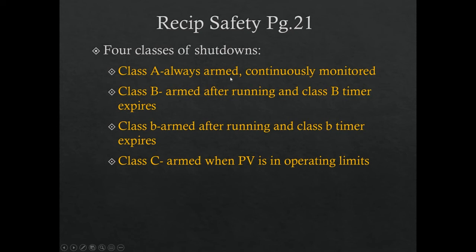So class A, always armed, continuously monitored. So these are usually your vibration controls, your temperature controls, pressure controls, all that kind of good stuff. But you'll see as we walk through the startup and shutdown process, different classes come into play at different times in the process. So you can't have all your class A's operating before the compressor's running, for example.